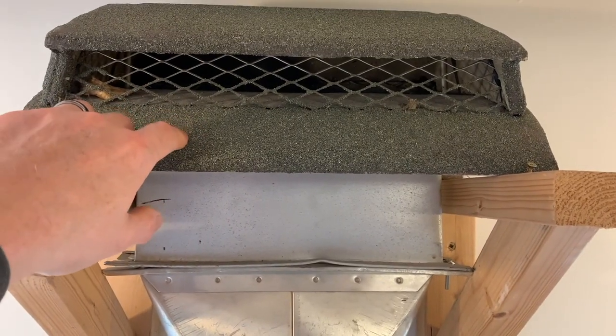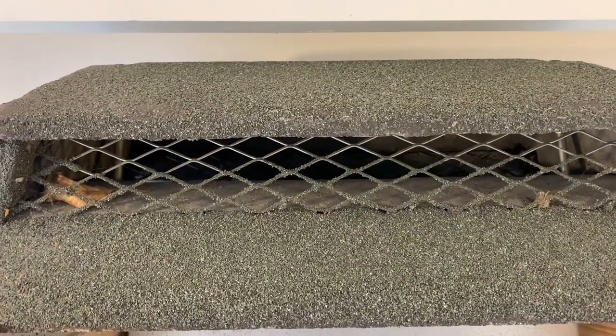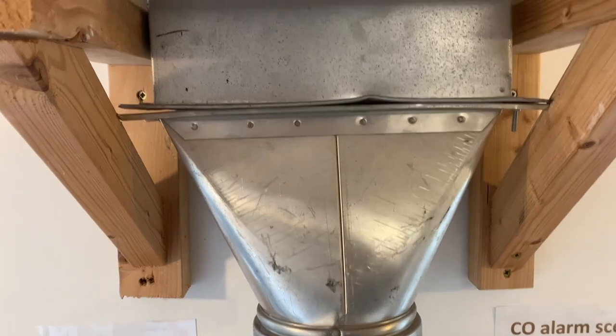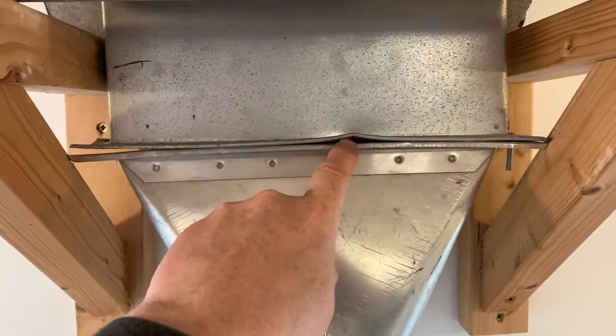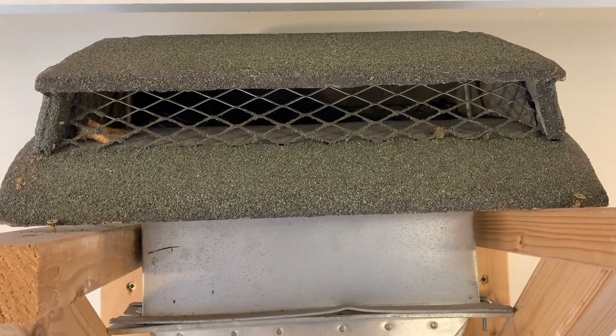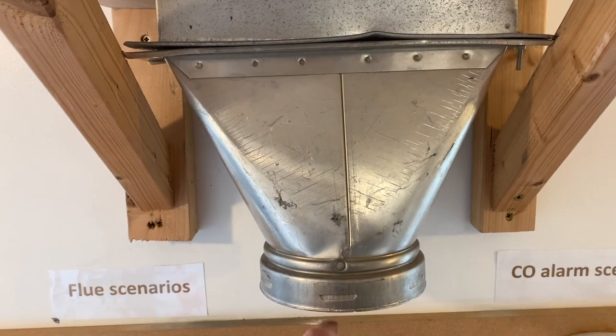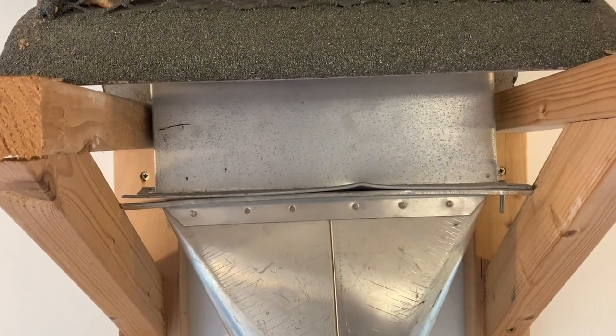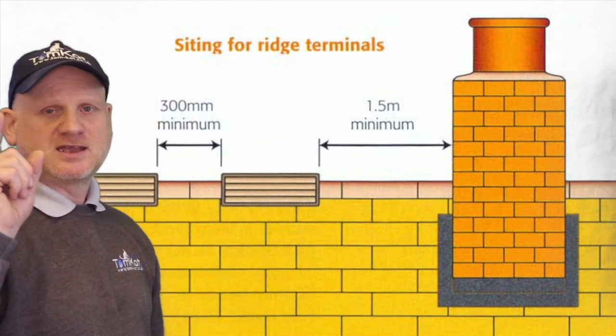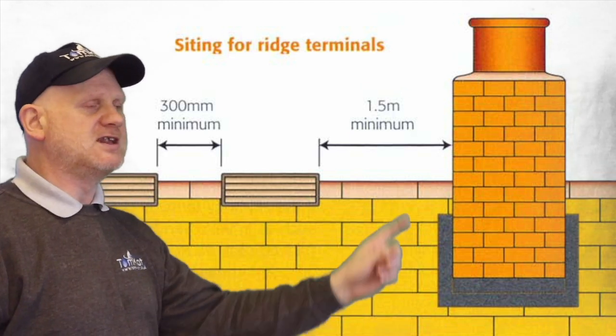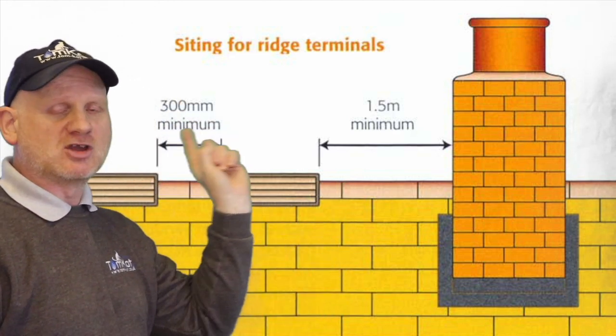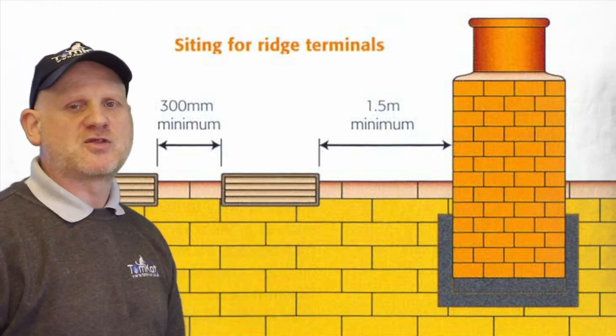This is the ridge terminal — what you would see on the roof, where the products of combustion come out. Inside the roof, you see the ridge adapter, which needs to be clamped on either side, have no damage, and have a gasket on the inside. The flue pipe connects to the ridge adapter. The ridge terminal must be more than 1.5 metres away from a structure or another chimney, and if you have two ridge terminals, they need to be a minimum of 300mm apart.